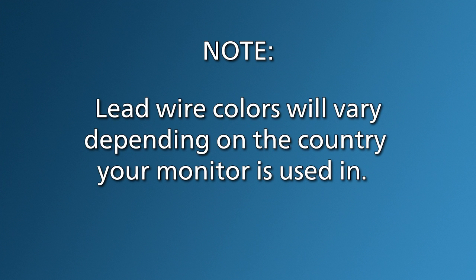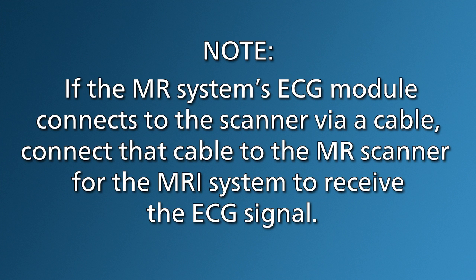Note, lead wire colors will vary depending on the country your monitor is used in. Note, if the MR system's ECG module connects to the scanner via a cable, connect that cable to the MR scanner for the MRI system to receive the ECG signal.